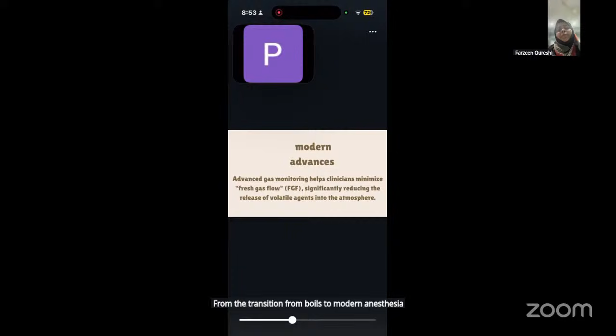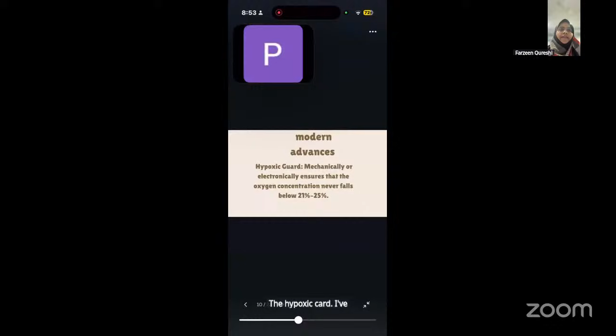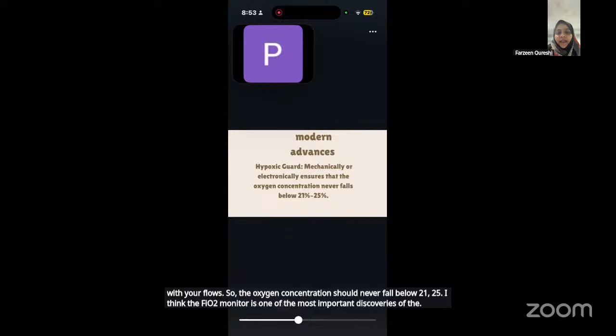Then we have an advanced gas monitoring system, which I said that you have to go for very low flow anesthesia. So the fresh gas flows being delivered less, I think, is one of the most important advancements from the transition from Boyle's to modern anesthesia, that we are polluting the environment lesser and lesser with the modern anesthesia machines. The hypoxic guard, I've mentioned it last, but definitely the most important on the list of the anesthesiologist. We do not want any hypoxia going to our patient at any cost. And that is only possible when the inbuilt systems of the anesthesia machine are working intact and in tandem with your flows. So the oxygen concentration should never fall below 21-25. I think the FiO2 monitor is one of the most important discoveries of the century.